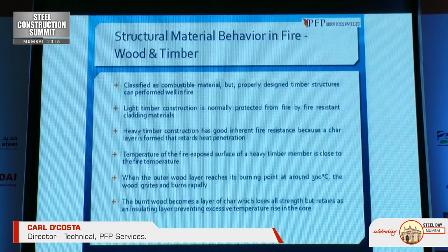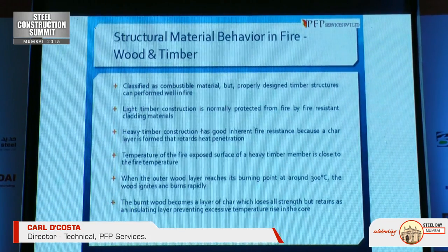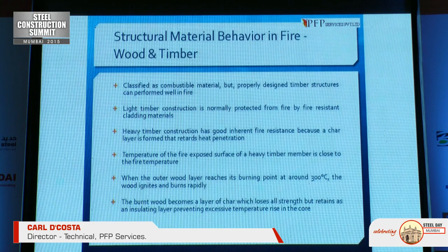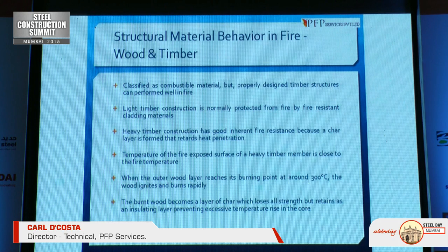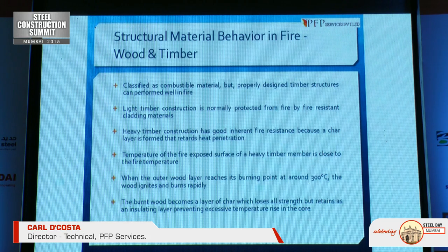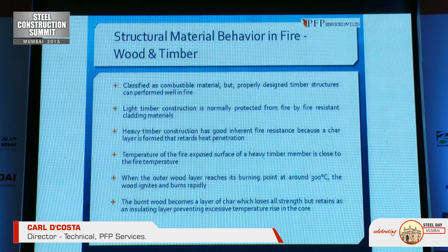Wood and timber are not very much used in construction, but are classified as combustible material. However, properly designed timber structures can perform well in a fire. Light timber structures are normally protected by fire-resistant cladding. Heavy timber construction has good inherent fire resistance because a char layer is formed that retards heat penetration. When the outer wood layer reaches its burning point of around 300°C, the wood ignites and burns. The burned wood becomes a layer of char, which loses all strength but retains an insulating layer, preventing excessive temperature rise in the core.